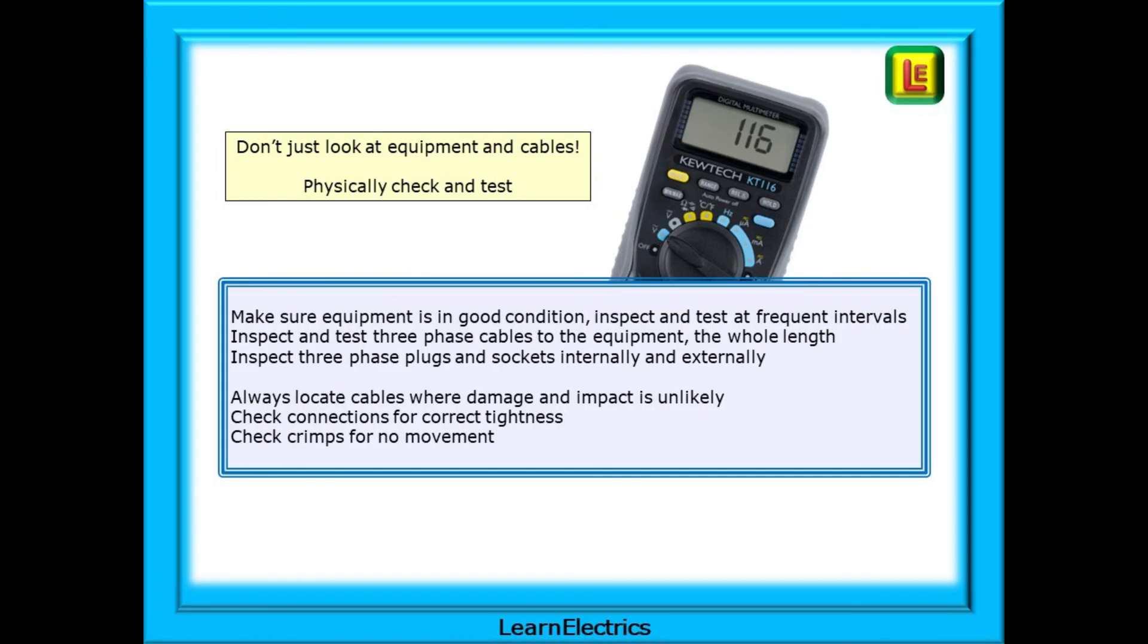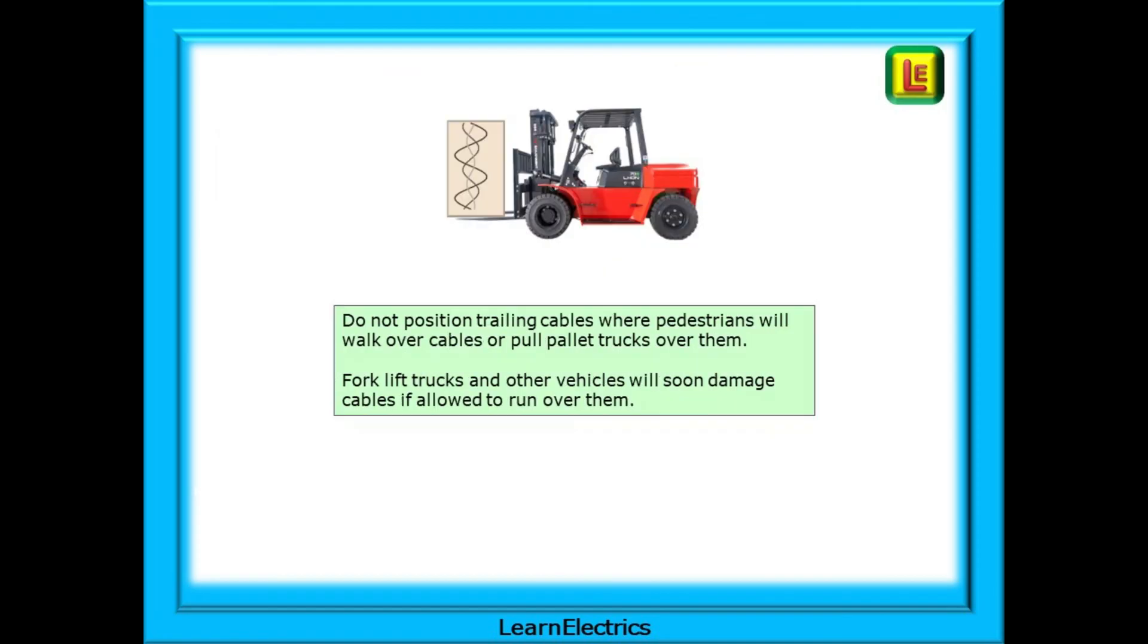Inspect and test three-phase cables that go to the equipment the whole length of the cable. Inspect three-phase plugs and sockets internally and externally. Locate cables where damage and impact is not likely and check connections for correct tightness and check crimps for no looseness. Vehicle and pedestrian movement is another possible source of damaged or broken connections. Do not position trailing cables where pedestrians will walk over the cables or pull pallet trucks over them. And forklift trucks and other vehicles will soon damage cables if allowed to run over them.